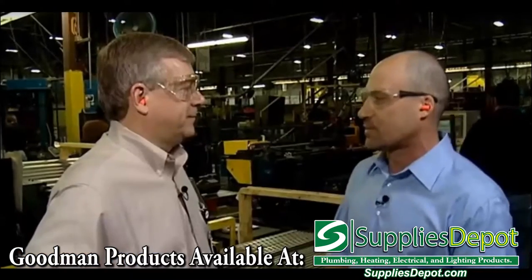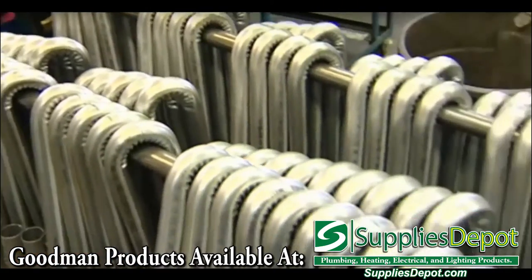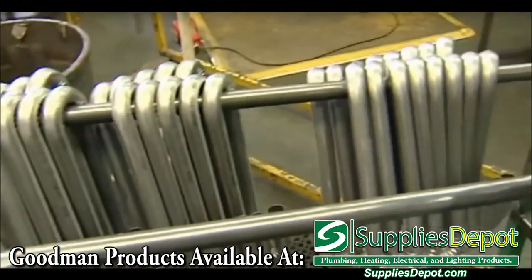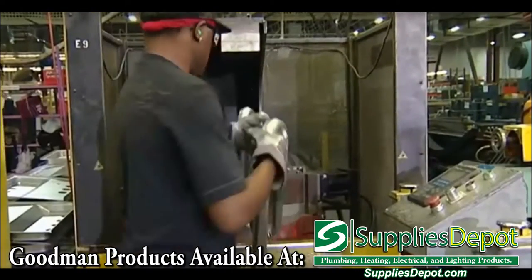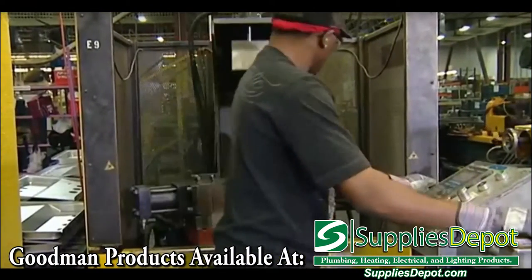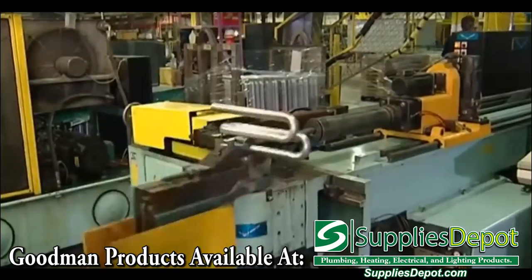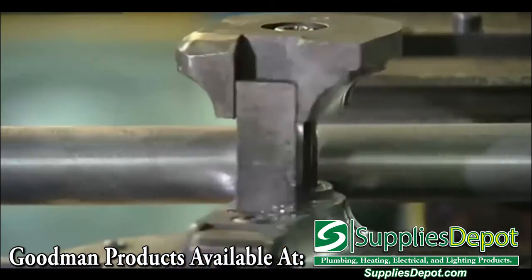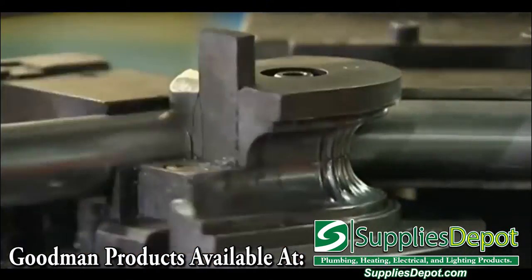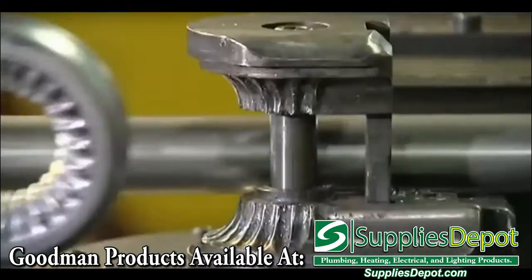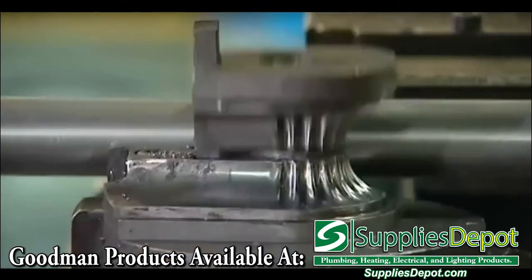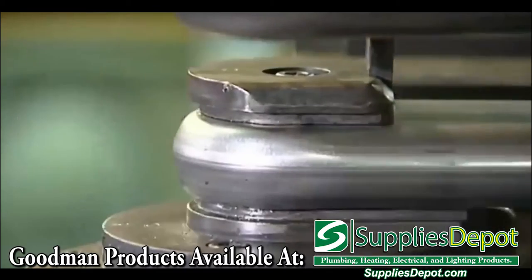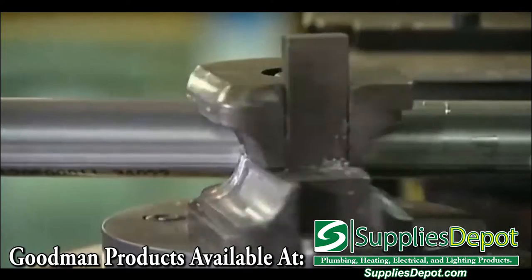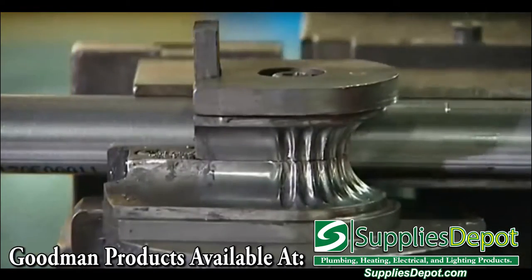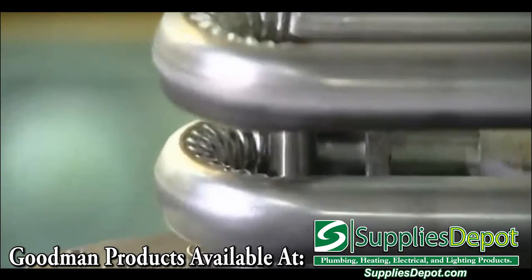Also with our tubes, Dave, we pressure fit those together. There's two different diameters. That reduces the velocity inside the tube, which adds to heat exchange. Another piece of technology that we have with our heat exchanger is wrinkle bend technology. Now that puts a wrinkle on the inside radius of that tube, does two things. It adds air turbulence inside that for added heat exchange, and it also keeps the wall thickness consistent throughout the outside diameter of that tube.